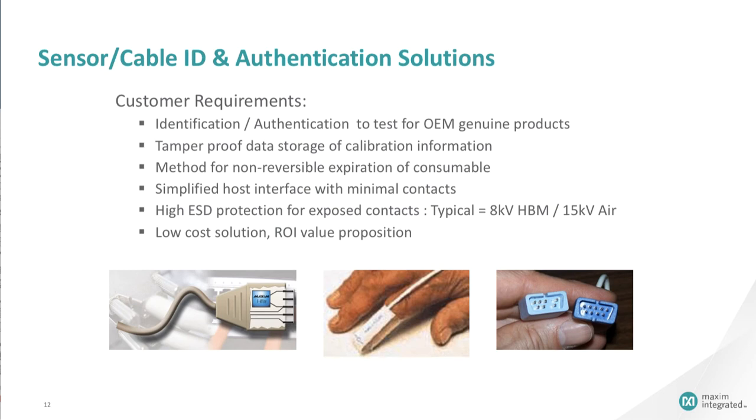The sensor/cable ID and authentication applications have these key requirements: The identification or authentication to test for OEM genuine products. Tamper-proof data storage of calibration information. A method for non-reversible expiration of consumables. A simplified host interface with minimal contacts. High ESD protection for exposed contacts, typically 8 kilovolts with a human body model or 15 kV in air. A low-cost solution because they have to have a good return on investment value proposition.